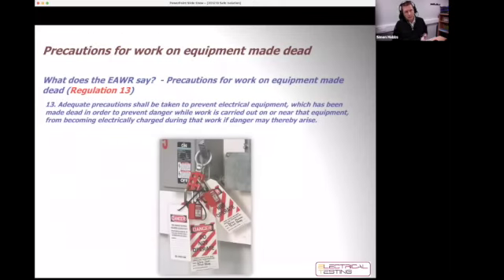Now they go on in the Electricity at Work Regulations, regulation 13, to take a next step, and that's precautions for work on equipment that has been made dead. So I've switched it off and I've isolated it. Regulation 13 says adequate precautions shall be taken to prevent electrical equipment that has been made dead, in order to prevent danger while working on or near it, from becoming electrically charged during that work if danger may thereby arise. So not only have we got to switch it off, we've got to make sure it doesn't come back on, but they do use the term in the law 'electrically charged'. So it may be that it needs to be prevented from being charged from another source or another activity somewhere else. So they're the legal definitions with regards to isolating the supply and making sure it stays isolated.